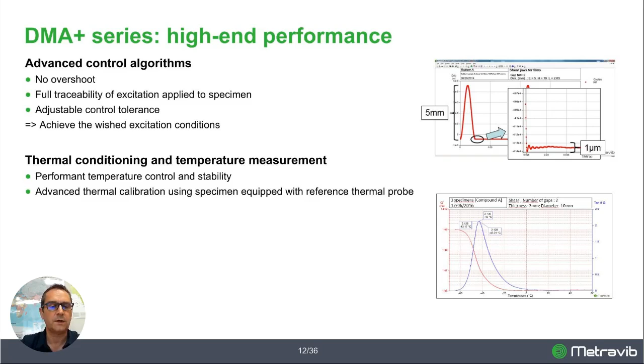The last point relates to ergonomics, which is especially important for the operator, but is also key for productivity. In the design of the DMA+ series, no hardware has to be exchanged to perform the test and to cover the whole analysis range, in terms of frequency, force and displacement. All the transducers are included in the system, so a frequency sweep, for instance, can be swept from low frequency to high frequency without having to change any hardware or any transducer. That makes it possible to do continuous tests in a single shot, whatever the range of analysis is.